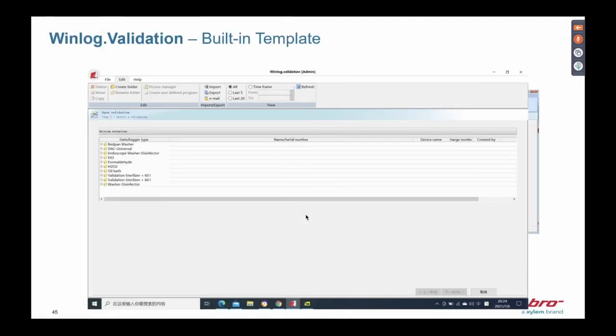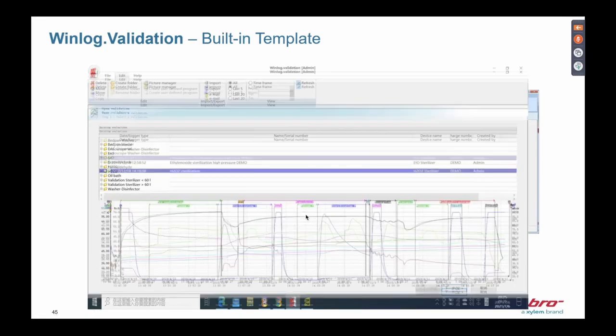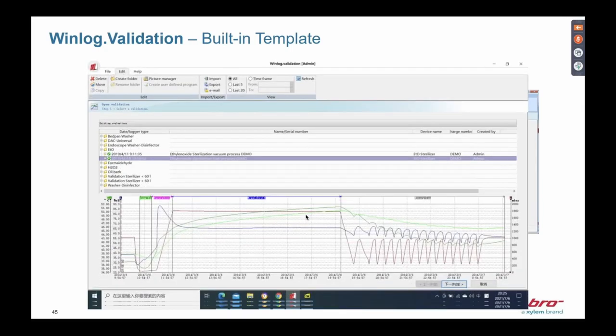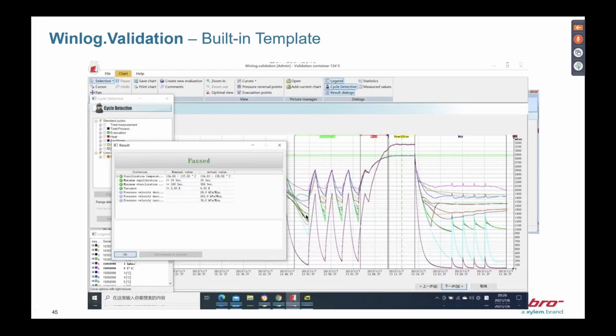One function I'd like to highlight is the built-in template feature. In Winlog.Validation, there are many pre-built templates to choose from. You can see how a sterilization cycle looks, review the parameters, and simply modify them using these templates. Winlog.Validation can also automatically determine — based on the criteria you set in the software — whether a run passed or failed, and if it failed, it will show you the reason in the result box.